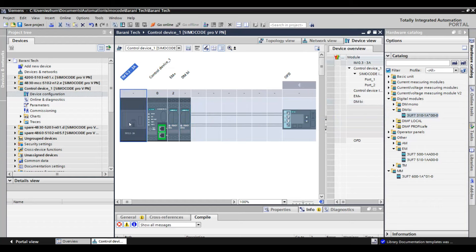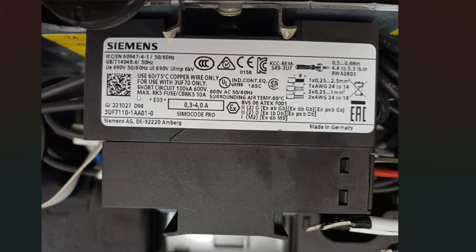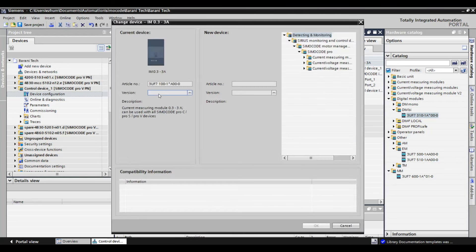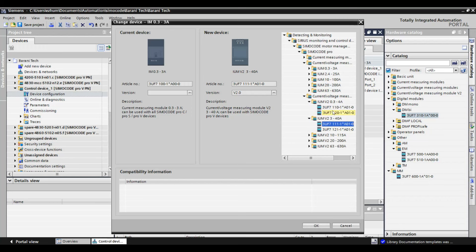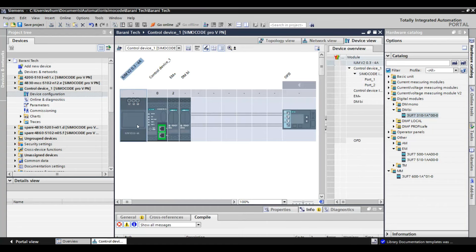Now I am going to check the CT part number. By default, the CT ratio is 0.3 to 3 amps and the part number is different, but the actual CT ratio is 0.3 to 4 amps. We have to note the part number and change accordingly. For changing this, just right-click on the CT and select 'Change Device.' On the right side, there are various current measuring device types. Check the CT part number which is exactly matching — here I got this part number correctly: 3UF7110-1AA01-0. It was exactly matching. Select this device and click OK. By this, we have done the hardware configuration successfully.